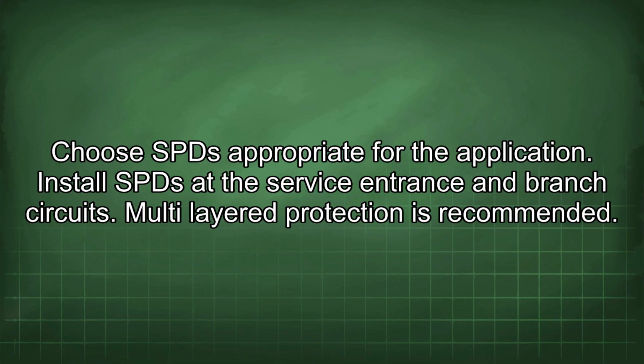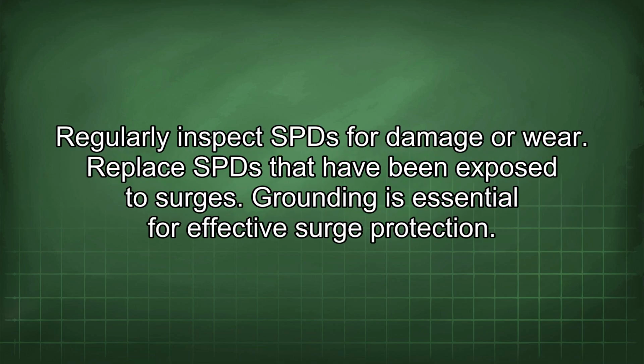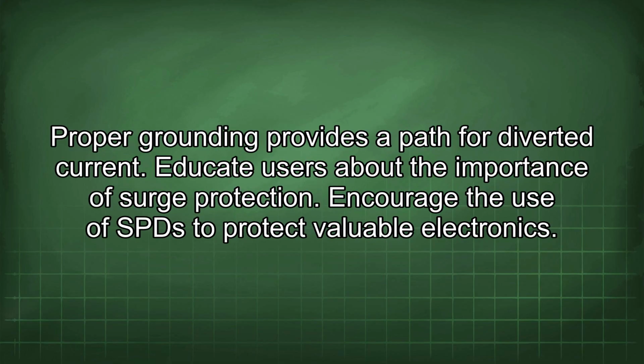Install SPDs at the service entrance and branch circuit. Multi-layer protection is recommended. Regularly inspect SPDs for damage or wear. Replace SPDs that have been exposed to surges. Grounding is essential for effective surge protection. Proper grounding provides a path for diverted current. Educate users about the importance of surge protection. Encourage the use of SPDs to protect valuable electronics.